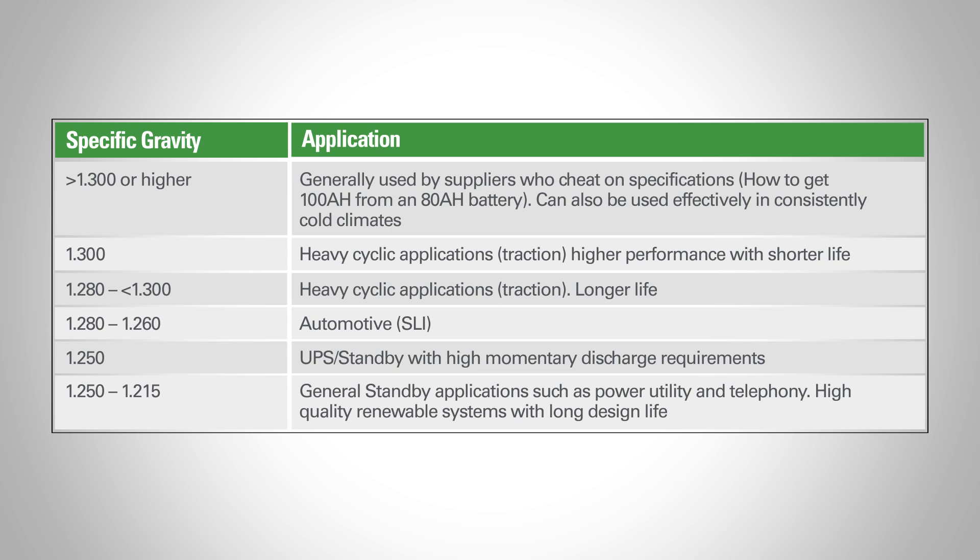Heavy cyclic and traction battery applications commonly see specific gravities of around 1300. In the automotive market, 1280 specific gravity is typical, translating to a fully charged battery of around 12.8 volts. Batteries used in hot climates may ship with only 1260. UPS and standby batteries with high momentary discharge requirements typically use about 1250, while general standby and renewable energy systems may use as low as 1215.